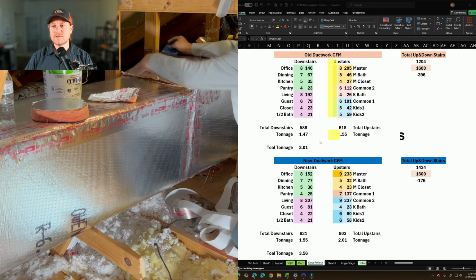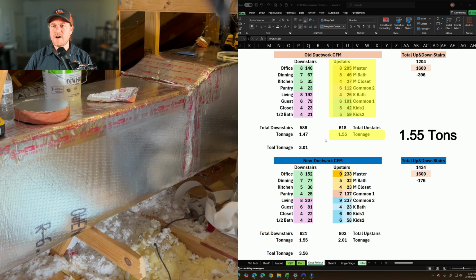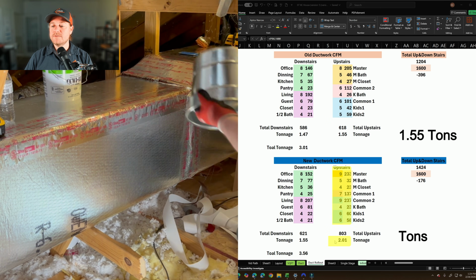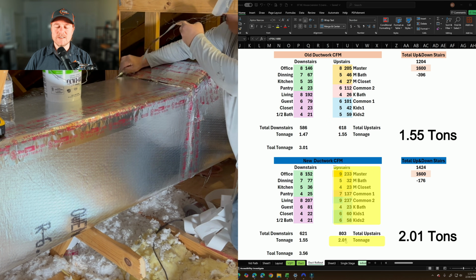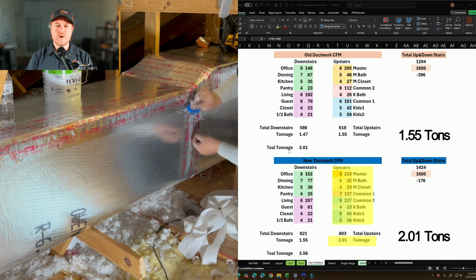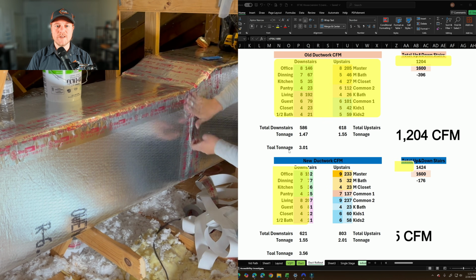And for the upstairs ductwork, it was able to push 1.55 tons of airflow, and now it's pushing 2 tons of airflow, which is a pretty decent increase in airflow. Overall, we went from 1200 CFM to 1400 CFM.